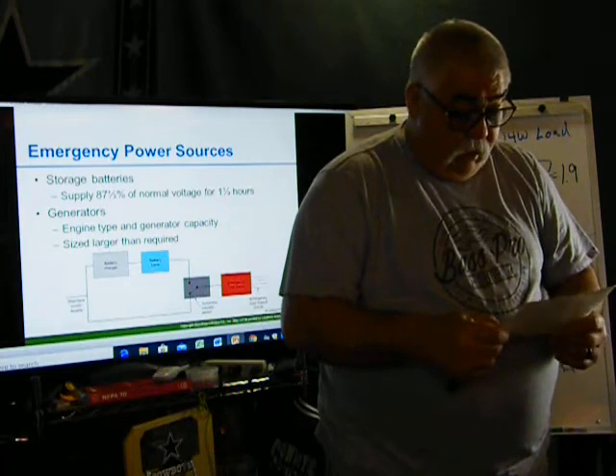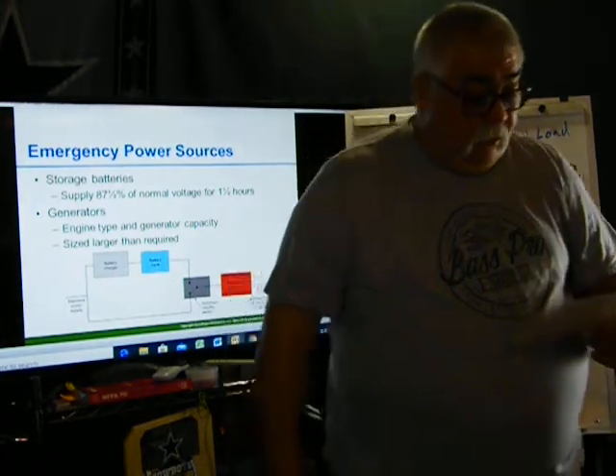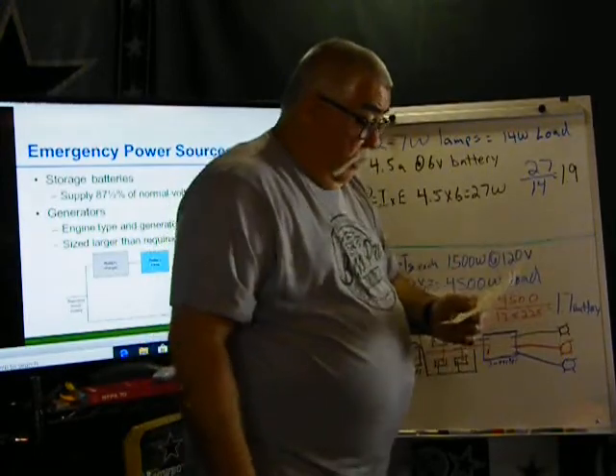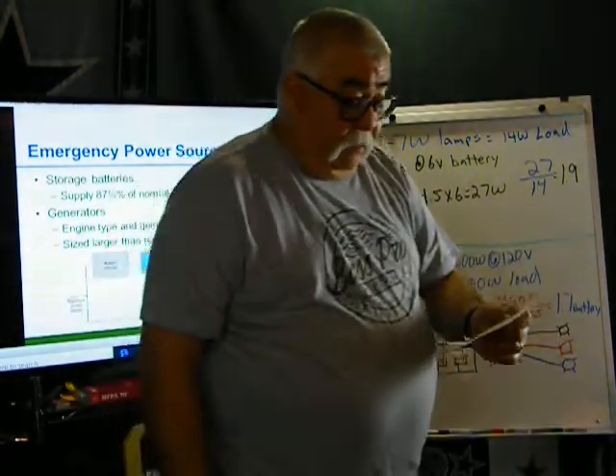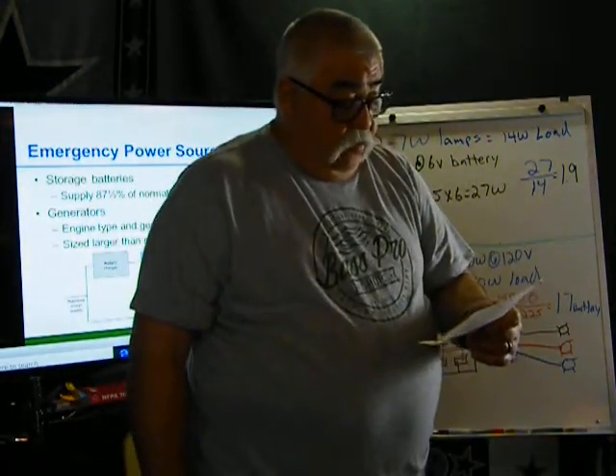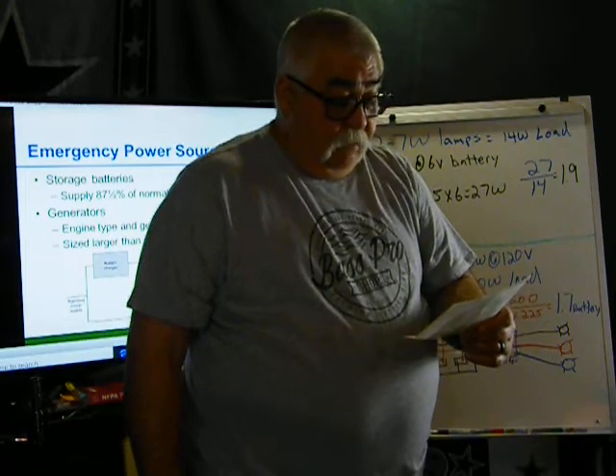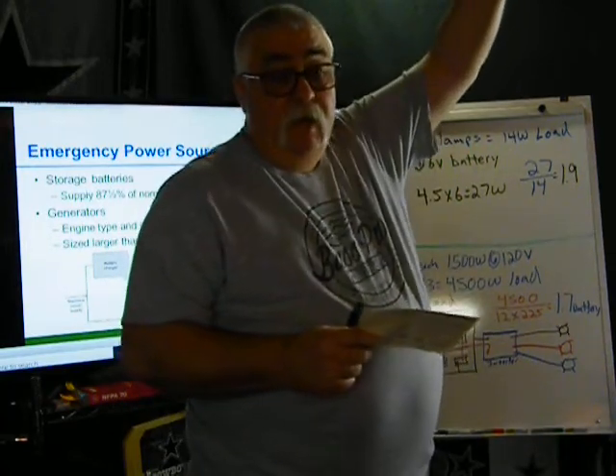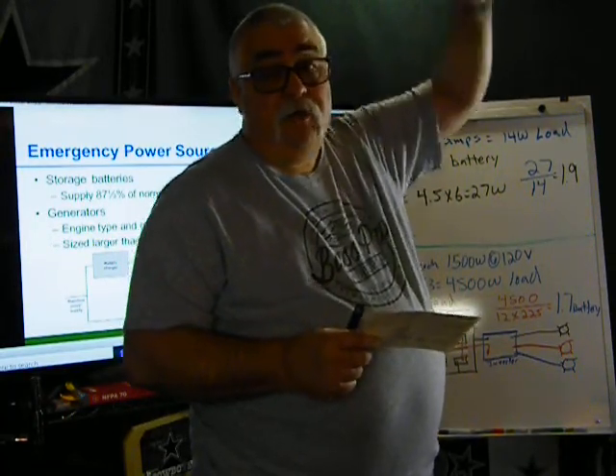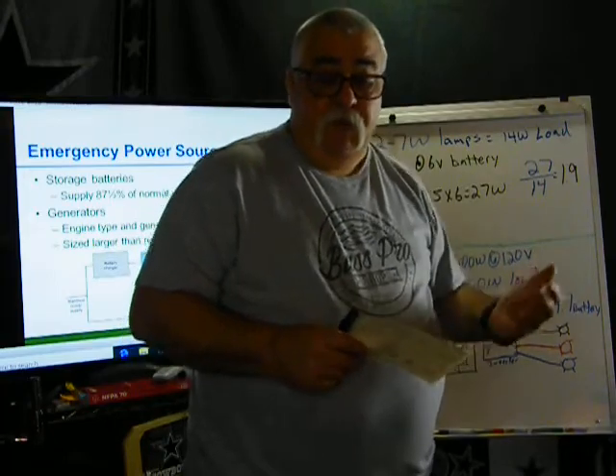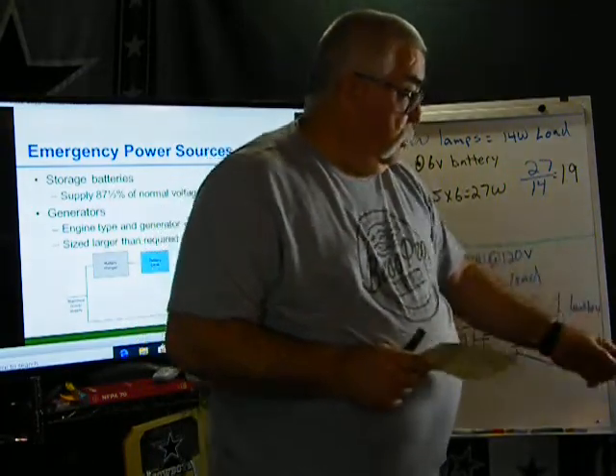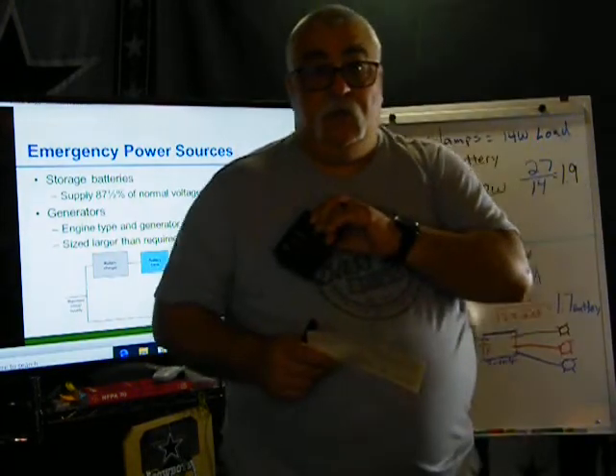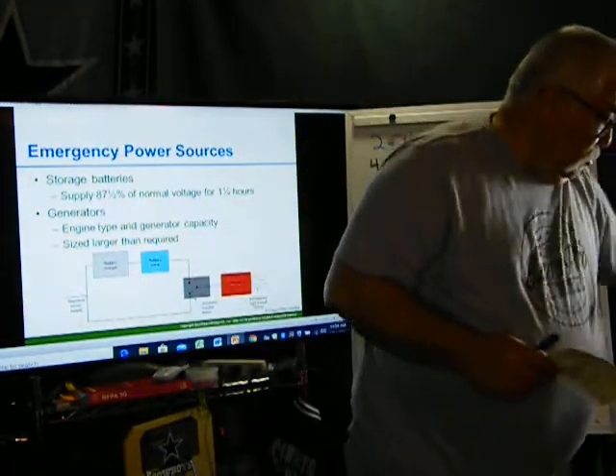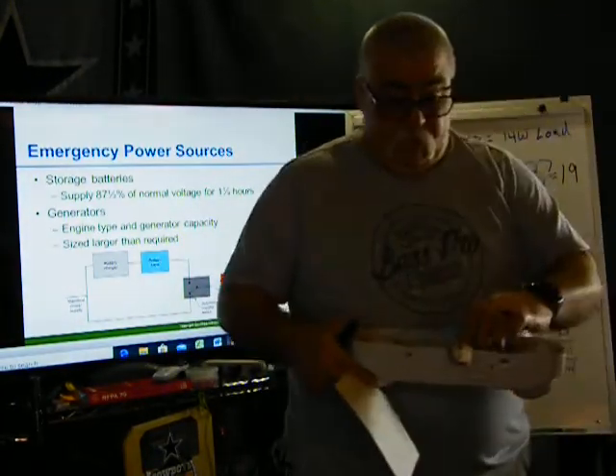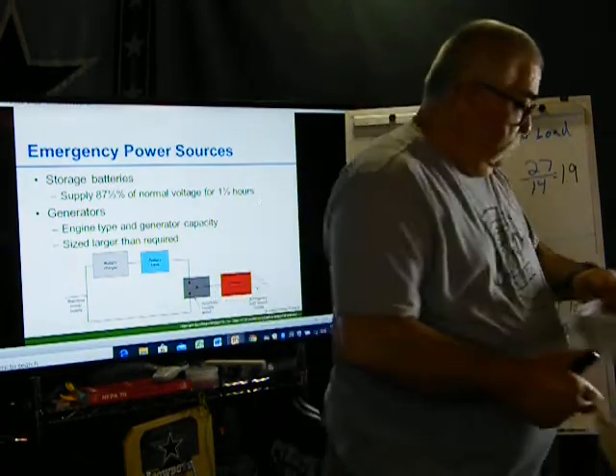But it also says inspection. The National Electric Code and NFPA Life Safety Code require that routine tests be performed as follows. Once a month, each unit should be tested by interrupting the power supply for at least 30 seconds. That means you go out there and push the button and let it come on. See, it comes on for 30 seconds. You make sure it stays on, it doesn't go out. Okay, so you're testing to make sure that this battery's still good. You're testing to make sure that this electronic board is still working. Okay?